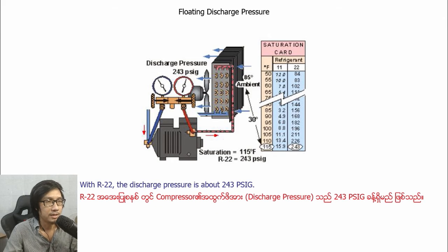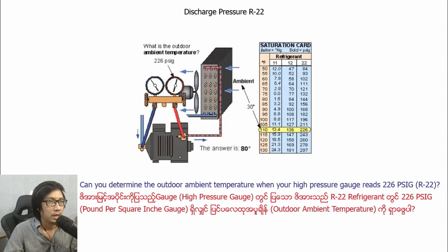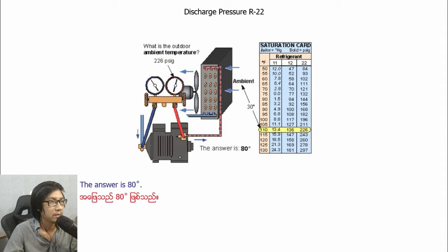With R22, the discharge pressure is about 243 pounds per square inch gauge. Can you determine the outdoor ambient temperature when your high pressure gauge reads 226 pounds per square inch gauge for R22? The answer is 80 degrees.